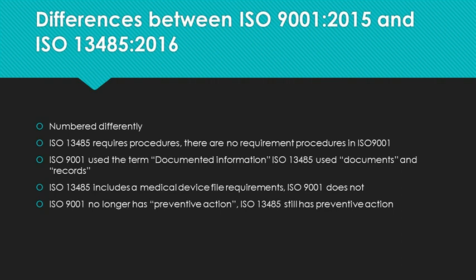ISO 13485 has a specific section on medical device files and their content, and a section on meeting regulatory requirements. This has never been a specific requirement of ISO 9001. However, regulatory agencies should be considered interested parties when implementing ISO 9001-2015. Finally, ISO 9001 no longer has a section on preventive action and considers it part of corrective action. ISO 13485 does have a section on preventive action. That is most of the key differences between the two standards.